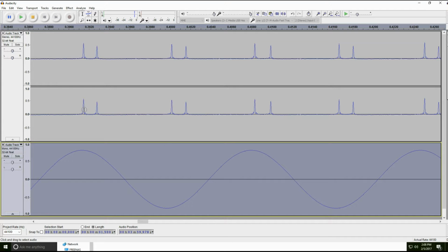Whereas at the bottom, we're seeing the same. So that tells me that when the voltage gets over a certain amount as it makes this wave, something is not able to insulate properly. So chances are what's happening is we're having a flash or a crackle or something local to that pole.